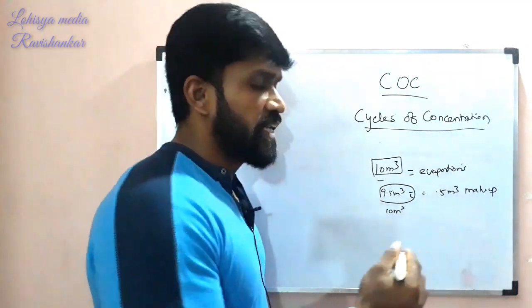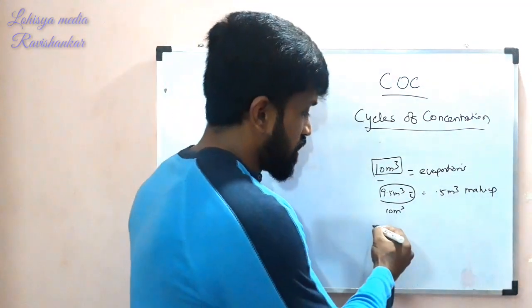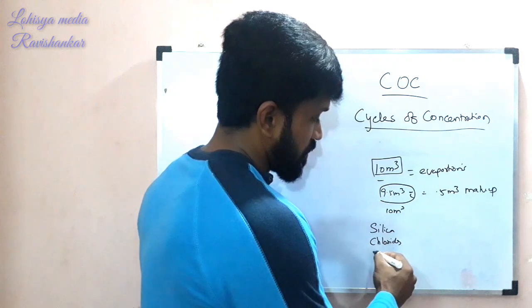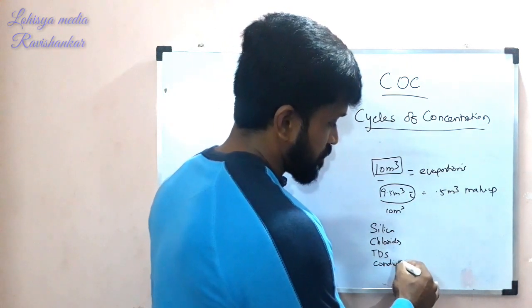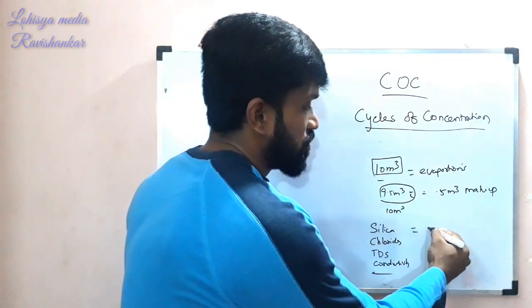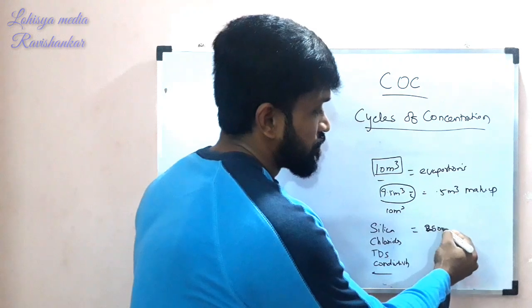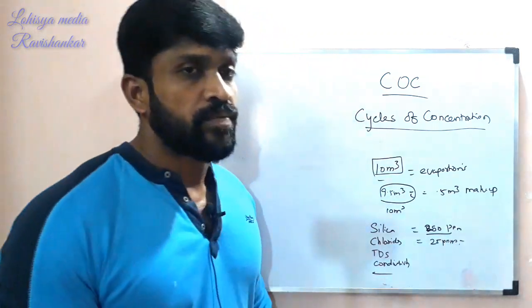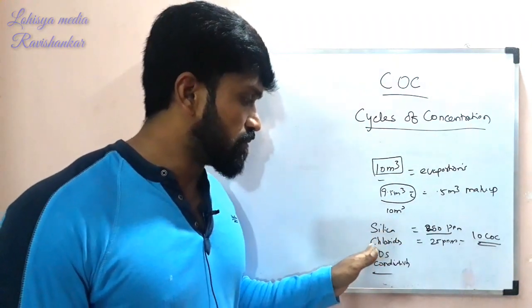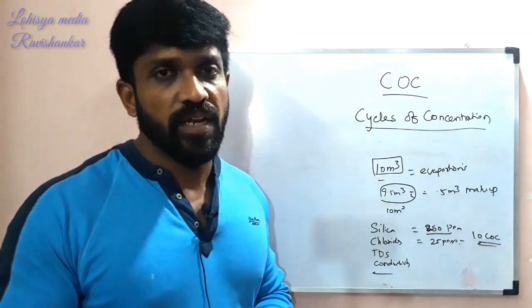The key parameters to monitor are: silica value, chlorides value, TDS, and conductivity. For example, if silica in the circulation water is 250 ppm and in the makeup water it is 25 ppm, then that gives you 10 COC — 10 Cycles of Concentration. Maintaining silica, chlorides, TDS, and conductivity allows you to maintain the cooling tower.